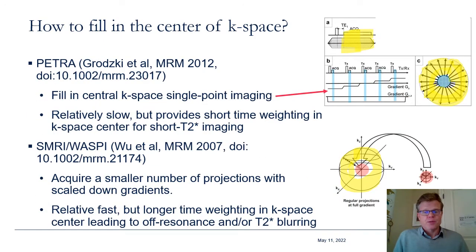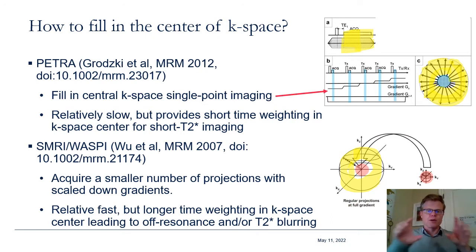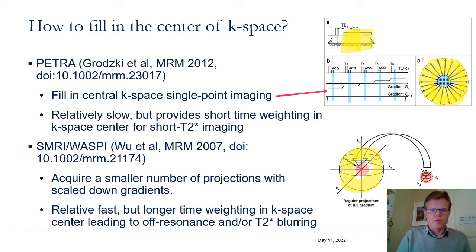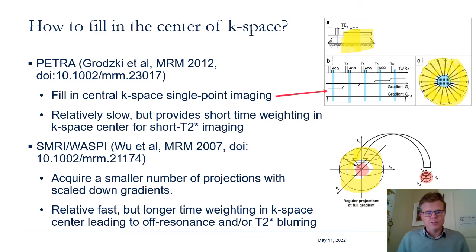There are a couple of popular and effective strategies for filling the center of k-space. One is called PETRA — a single point imaging technique. The outer region of k-space is filled with the radial projections already discussed, and to fill the center, we go point by point each TR, with each TR sampling just a single point of the central k-space region. A single point is relatively slow, but it provides very short TE weighting on the k-space center data, which is advantageous for short T2* imaging.